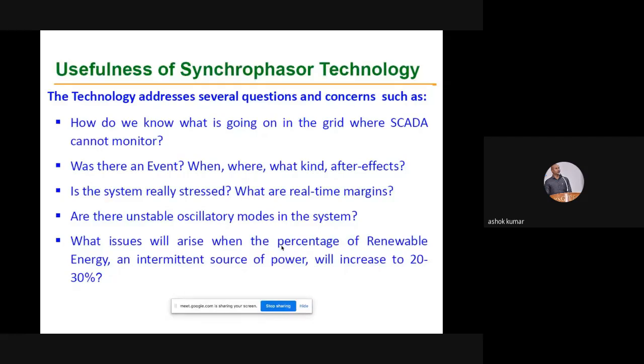Apart from that, one more parameter is not being considered as of now, but it is going to become a very big trouble in future: the frequency generated in the range of 2 kilohertz to 150 kilohertz, called supraharmonics. How will my system react? The system will get stressed when these supraharmonics take place. These supraharmonics occur whenever you implement a system consisting of semiconducting devices.